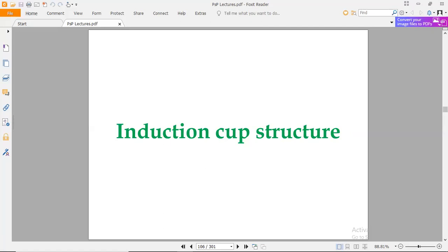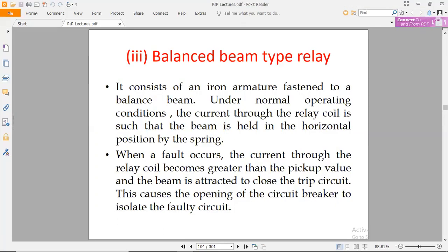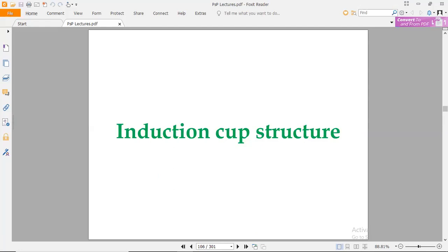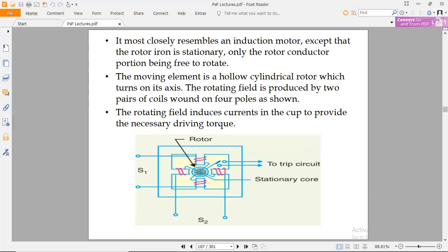In the previous session, we discussed some scenarios related to relays, the balance beam type and other aspects related to protection relays, and then another category of protection relays: the induction cup structure. It most closely resembles an induction motor. You can see the structure of the winding resembles a single phase induction motor, except that the rotor iron is stationary, whereas in an induction motor the rotor is in the moving stage, only the rotor conducting portion being free to rotate. The moving element is a hollow cylindrical rotor which turns on its axis.